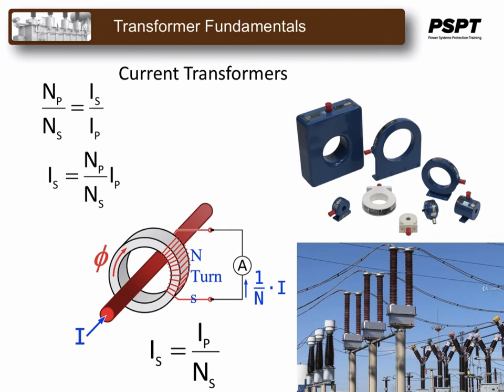This represents a small loss of load current, and albeit small, does affect the accuracy of the reading of the secondary. Current transformer losses, called errors, vary for different types of transformers and the burden or the load on the secondary. Standards have been established with acceptable error limits that transformers must fall within. Engineers must take this into consideration when designing, relaying, and metering setups.